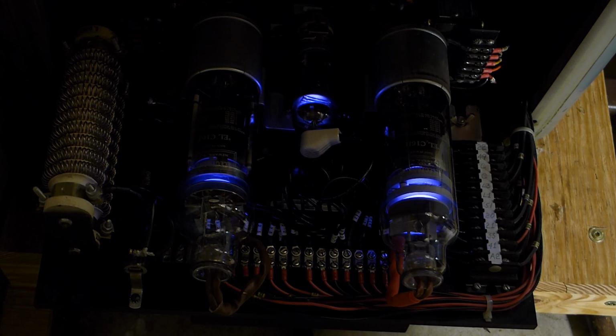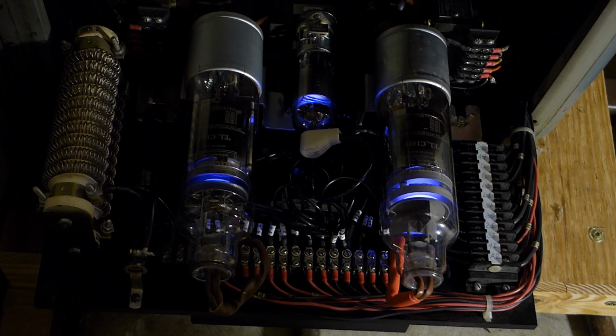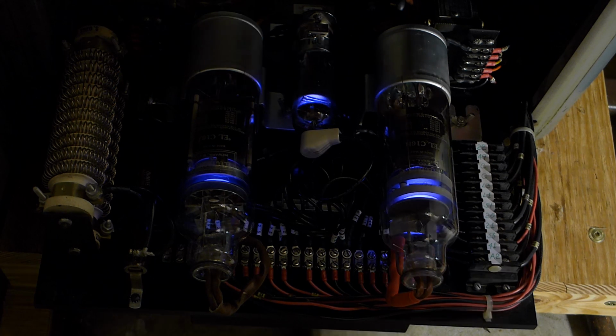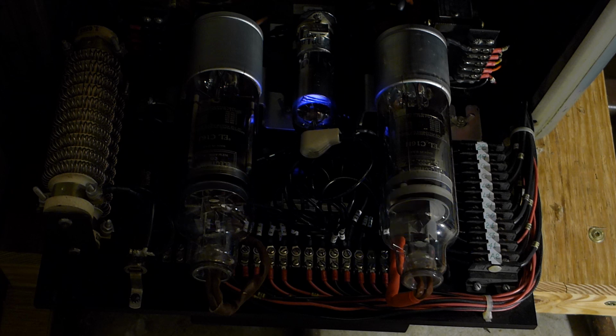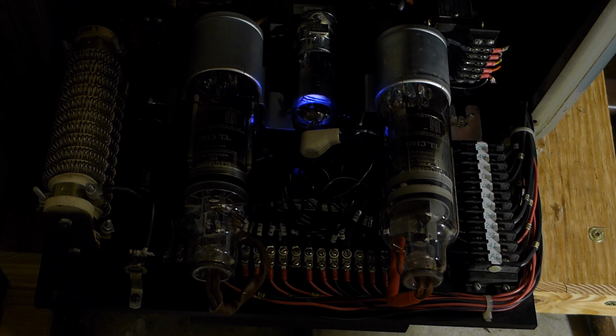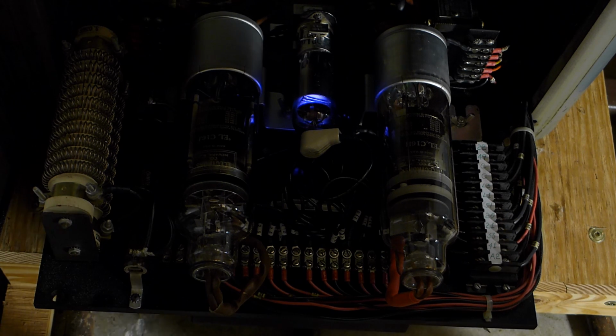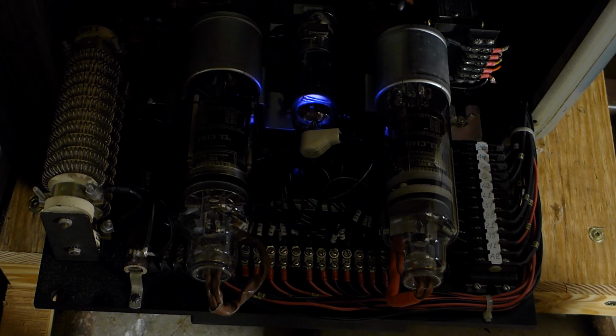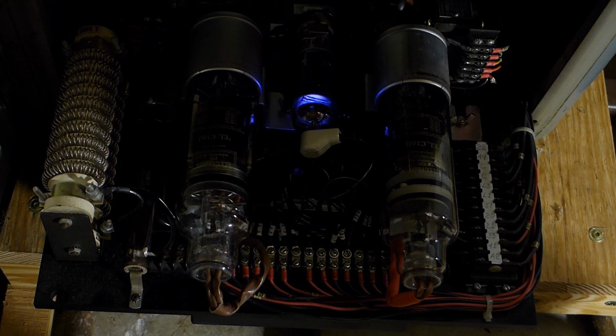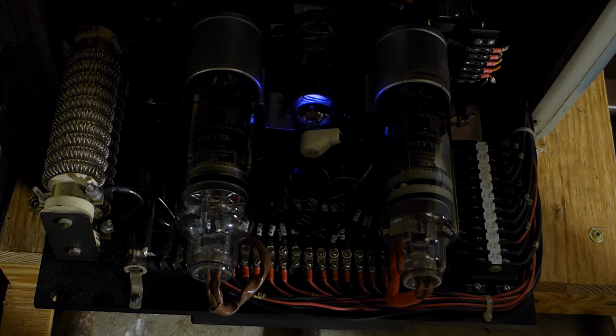So it's running pretty well. Sounds good, nice and smooth. Just a lot of transformer hum. It's not pulling any excessive current. It's just got a fair amount of noise. I mean, the motor hums and the transformer hums, but it's getting a dirty DC. It's essentially a DC pulse, 120 hertz.